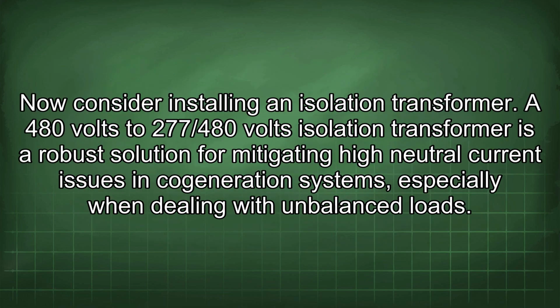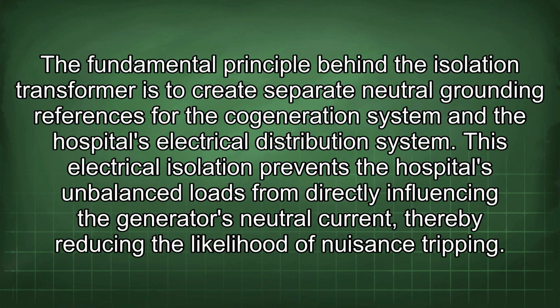Now consider installing an isolation transformer. A 480 volts to 277/480 volts isolation transformer is a robust solution for mitigating high neutral current issues in cogeneration systems, especially when dealing with unbalanced loads. The fundamental principle behind the isolation transformer is to create separate neutral grounding references for the cogeneration system and the hospital's electrical distribution system.